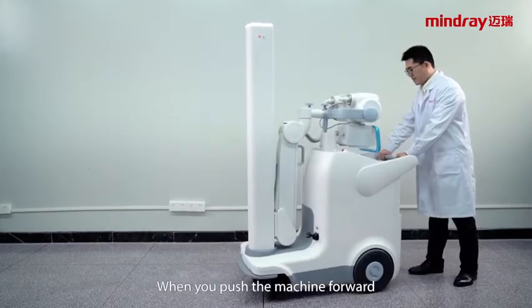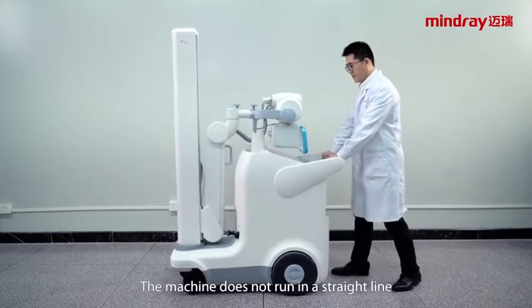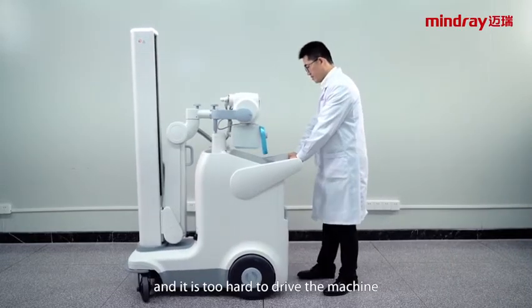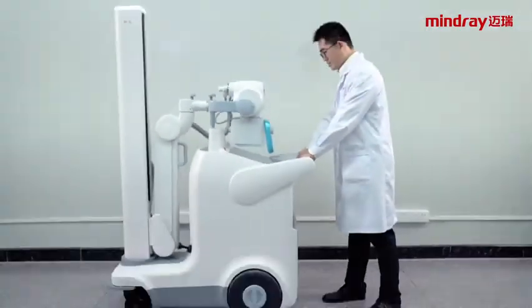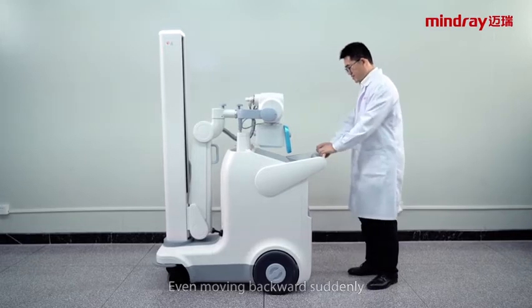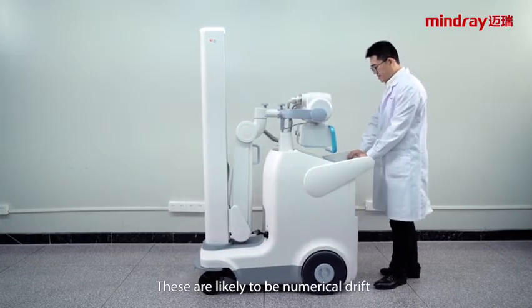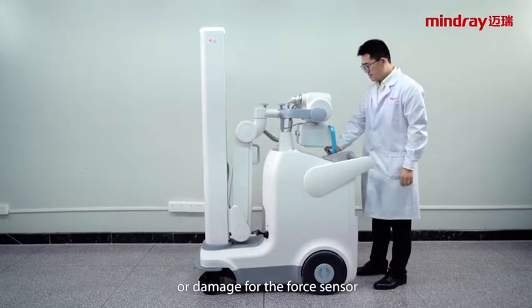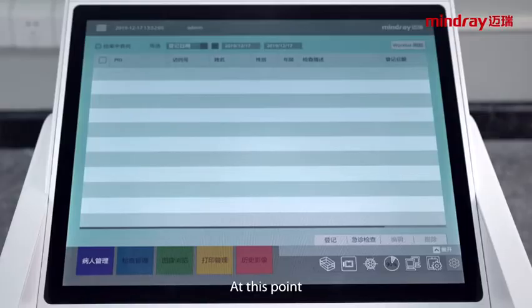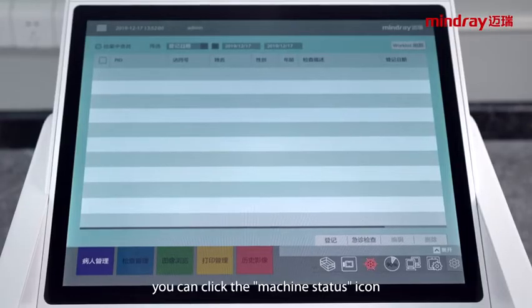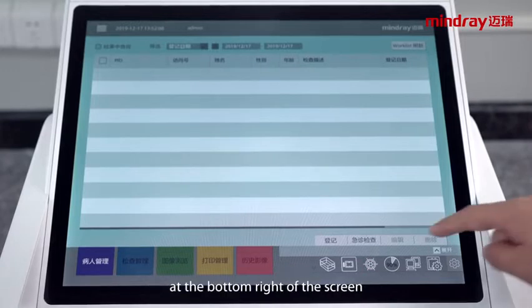When you push the machine forward, the machine does not run in a straight line and is too hard to drive, even moving backwards suddenly. These are likely to be numerical drift or damage of the force sensor. At this point, you can click the machine status icon at the bottom right of the screen.